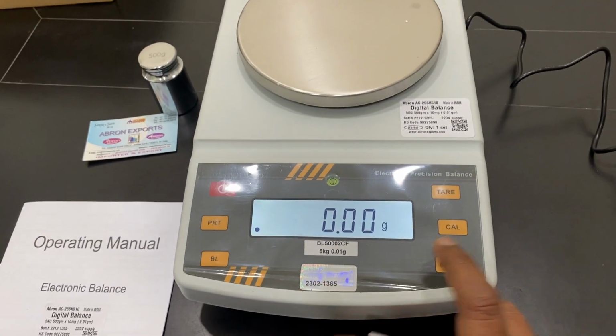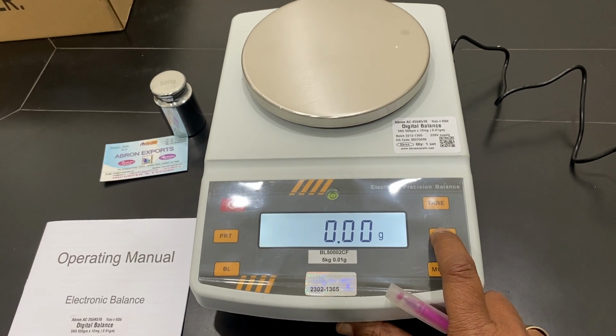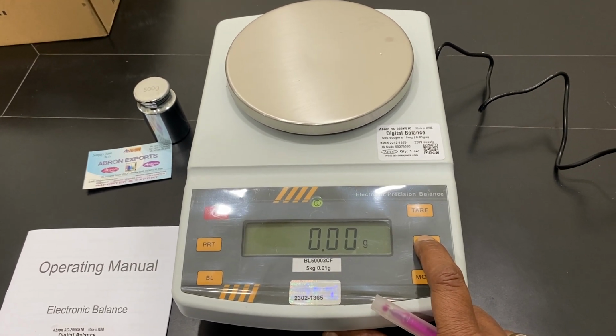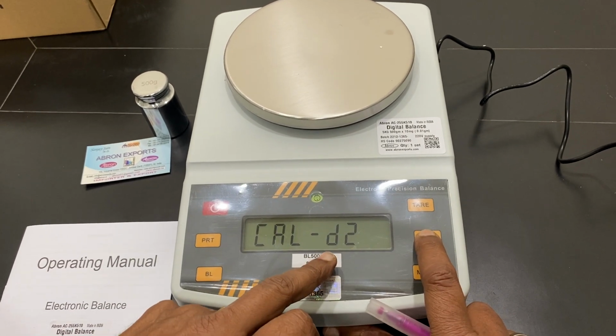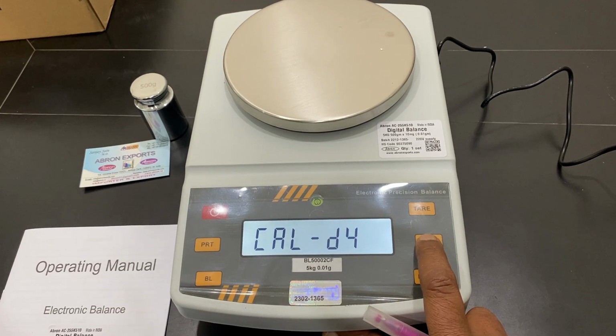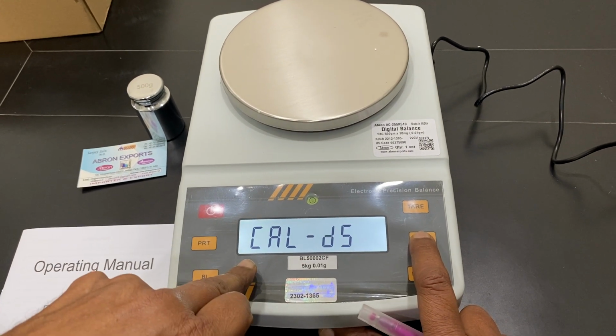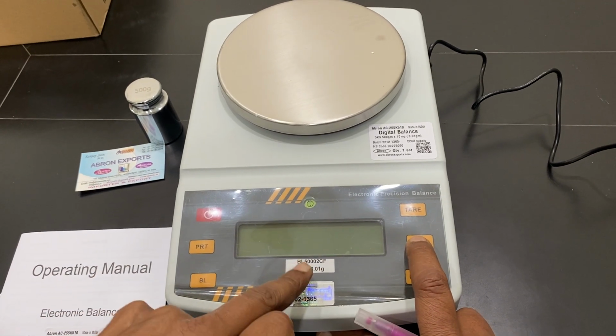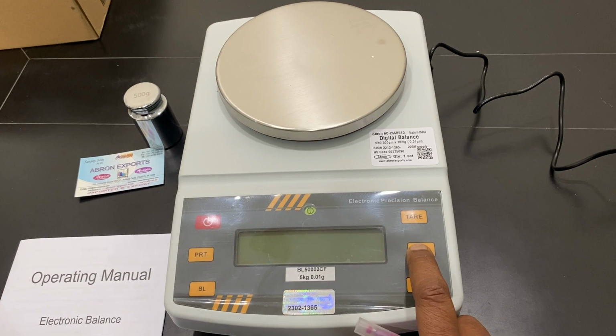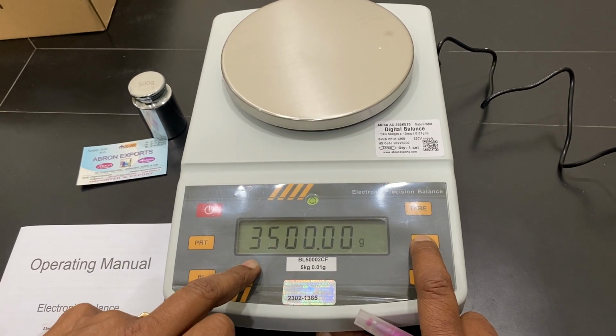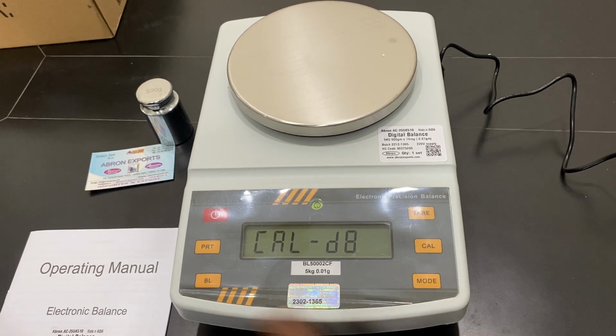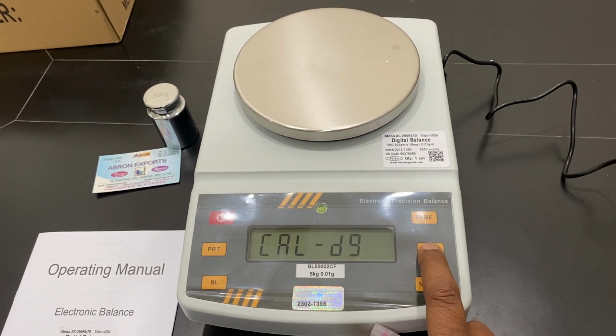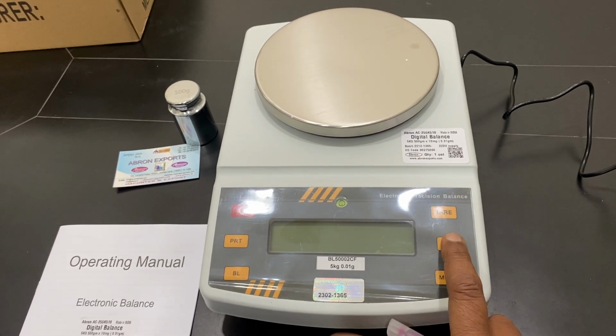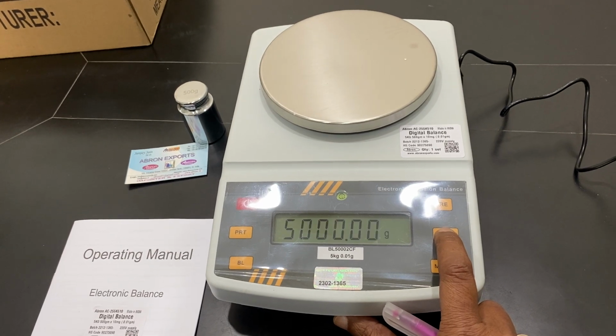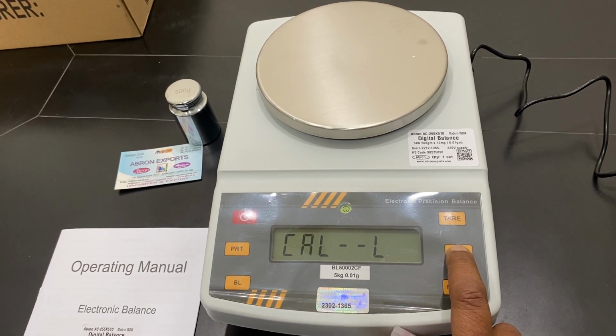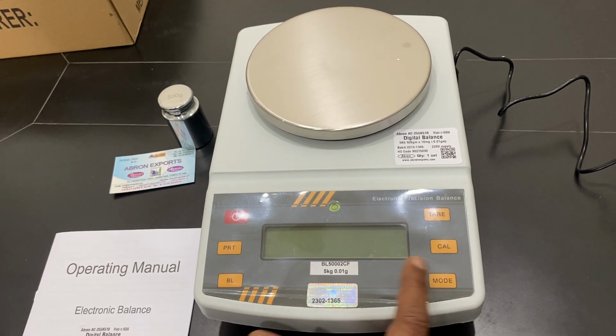If you want to calibrate on any other weight, if you have another weight, you can push it for 3 seconds. 1 is 500, 2 is 1000, 3 is 1500, 4 is 2000, 5 is 2500, 6 is 3000, and I press it again, 7 is 3500. You can go with any calibration, or you can switch it off and then go back to the same position. 9 is 4500, all means 5000 gram. I can calibrate, or do a linear scale calibration. This is on 500 gram.